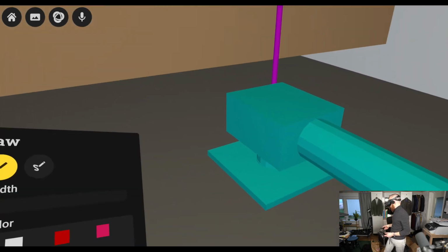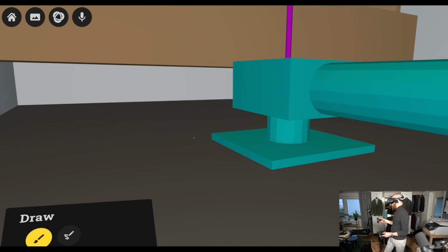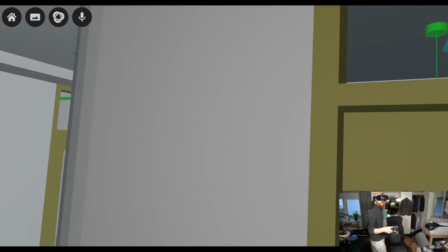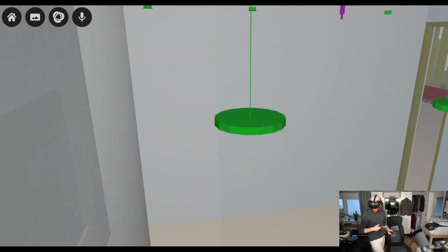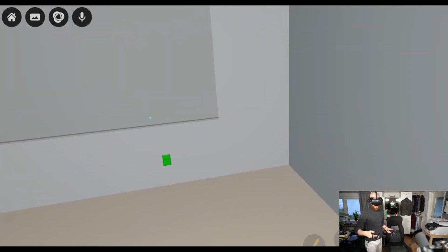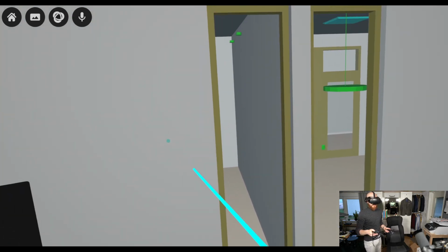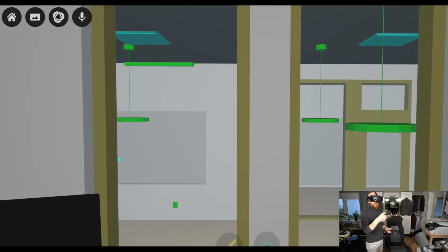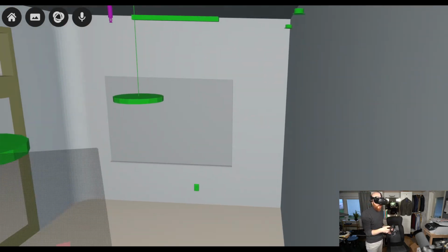So this is a pretty good way of solving it, because if you go through the corridor, you have a lower sound requirement if it looks like this, because here's a door, and when you have a door to the outside here, the sound requirement in this case could be a bit lower, like 35 or 40 dBs. Here you can see it also, how it's all connected together. Whereas if you were to make a wall pass through and you would go straight in to the next room this way through the wall, then you have a higher sound requirement, and in this case it could be 44 dB. So let's see why that could be a problem.